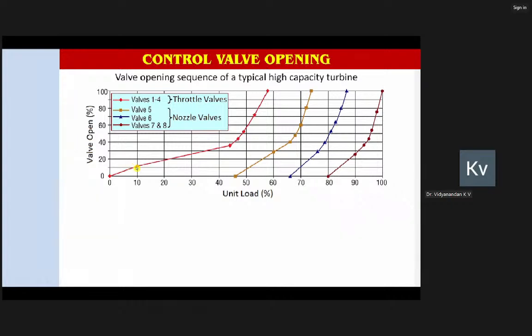Whereas if it is a nozzle governor, it will always be in sequence. Initially, 2 valves will open for mechanical stability and thermal equilibrium. So 2 valves diagonally opposite, say 1 and 3, will open, and once those 2 valves' opening reaches around say 20-25%, the third valve will open. Once the third valve opening reaches around say 20-25%, the fourth will open. Like that, sequentially valves will open. So this is the nozzle governor.